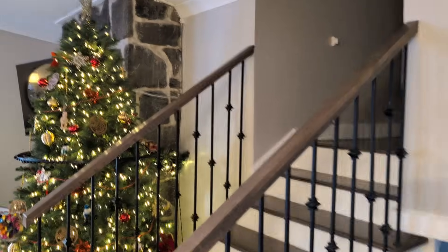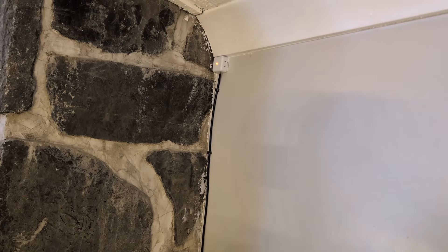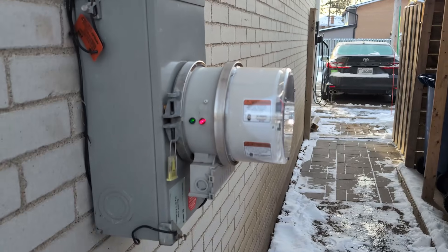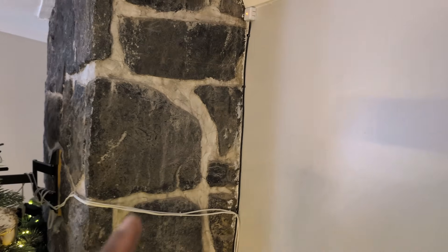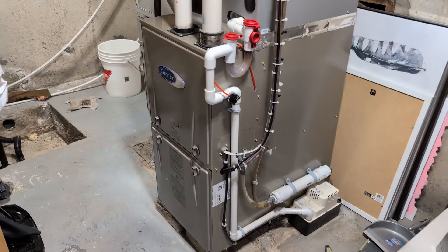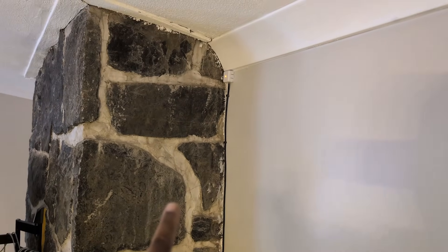For those who have Rate DT — dual energy — with Hydro-Québec, you probably know this light here. This light turns on when outside is minus 12 Celsius and colder. It's connected to the hydro meter outside, which in turn lights up this indicator when your rate is higher and also forces the heat pump to stop and switches to the gas furnace, forcing the usage of natural gas. So the rate is super high now at 26 cents per kilowatt hour. For us in Quebec that's expensive — our rates are usually between four and ten cents.